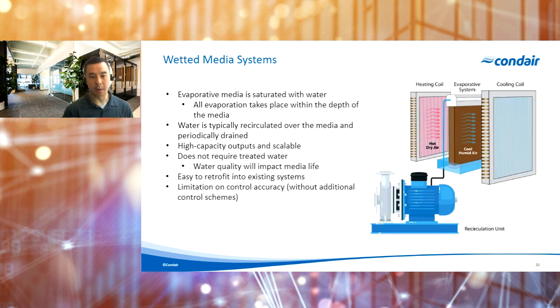The first type of system that we'll look at here is what we call a wetted media system. If you have heard the term swamp cooler before, it's effectively the same thing. What we have in this system is a wetted media placed directly in the airstream. That wetted media is typically a glass fiber based media. Depending on the application and where this is being installed, we do sometimes see a cellulose or paper based media used as well. But effectively, we are placing that media directly in the airstream. As warm, dry air passes through that media, water is evaporated off, and it cools and humidifies through that adiabatic process that we talked about earlier.